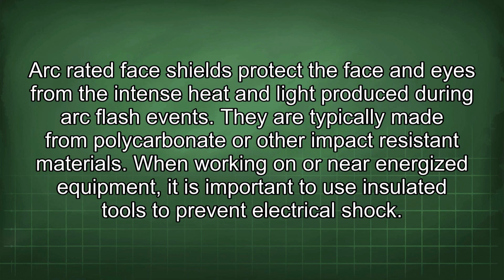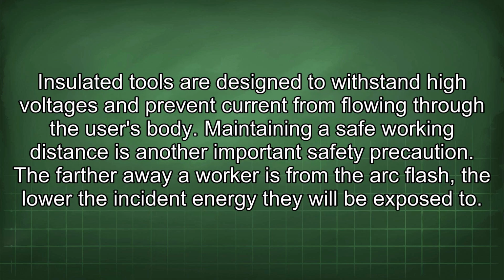When working on or near energized equipment, it is important to use insulated tools to prevent electrical shock. Insulated tools are designed to withstand high voltages and prevent current from flowing through the user's body. Maintaining a safe working distance is another important safety precaution. The farther away a worker is from the arc flash, the lower the incident energy they will be exposed to.